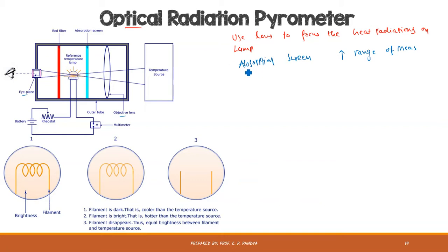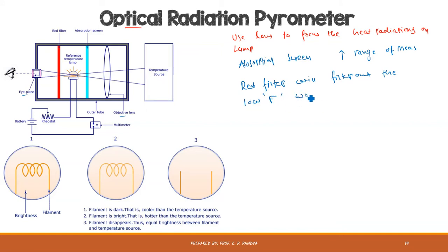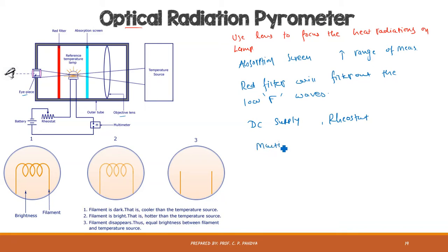These pyrometers are used to measure very high temperatures, and that is why the absorption screen is placed there. Between the eyepiece and the lamp there is a red filter, which is placed to allow only high frequency radiation — it filters out the low frequency waves of light. There is also an external DC power supply for the lamp, then a rheostat, and a measuring instrument; normally a multimeter can be used for measurement.